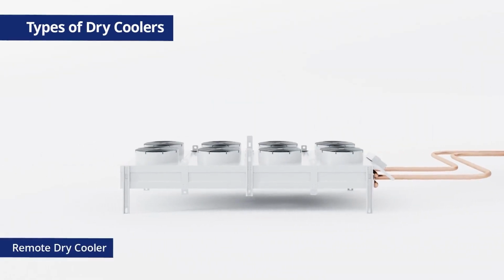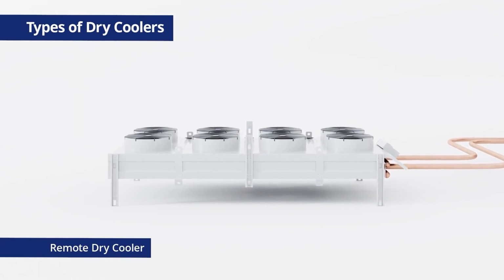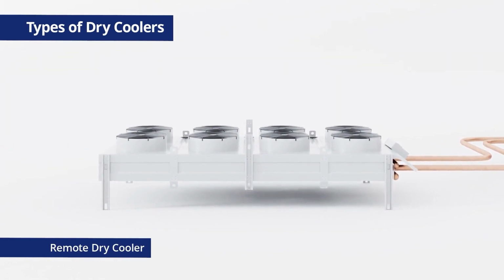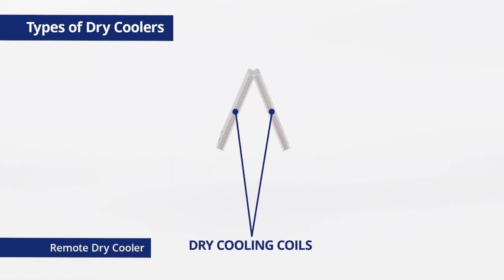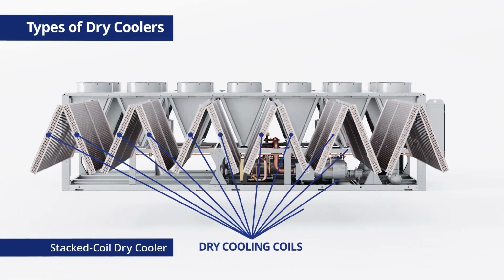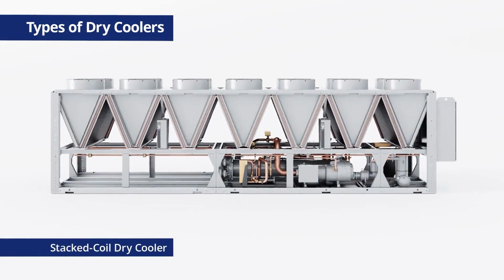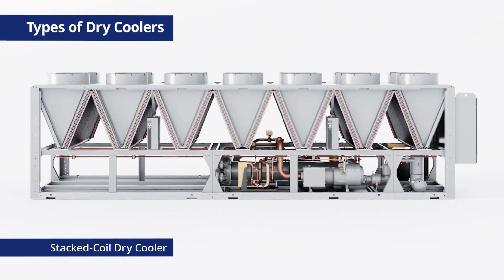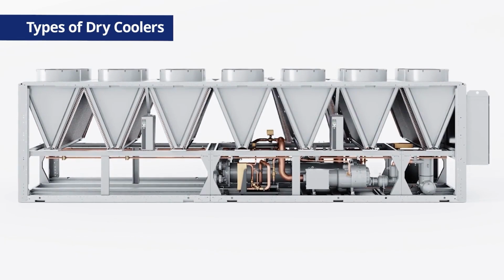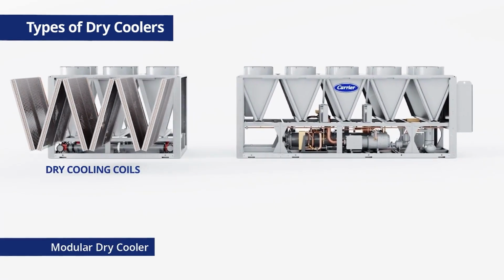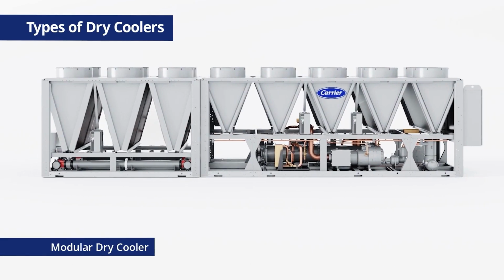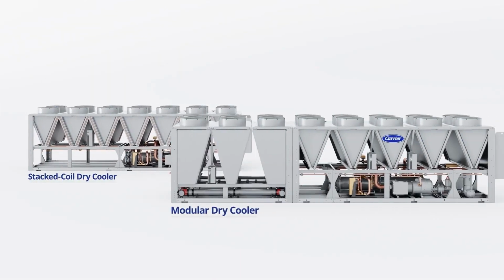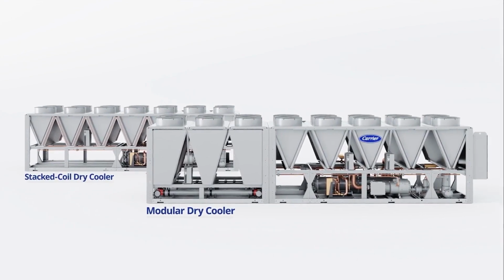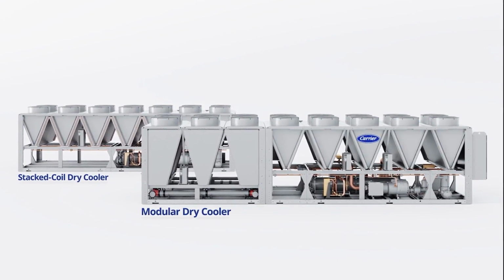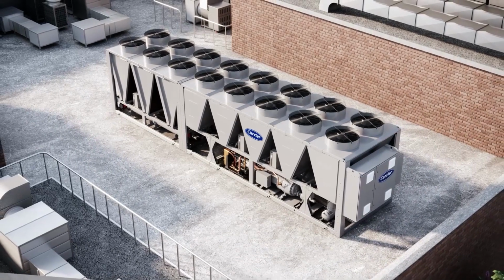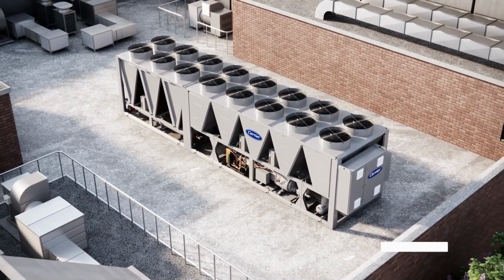The first style is a remote dry cooler. It's typically a general-purpose cooler that sits remote from the air-cooled chiller and is piped together. The second is a stacked coil dry cooler. In this case, the dry cooling coils are mounted or stacked next to the existing refrigerant condenser coils on the chiller. The third is a modular design. It attaches right onto the air-cooled chiller. The last two styles are preferred in many cases because they are designed to integrate directly with specific chillers right from the factory, improving performance. Where there is space available, the modular option can offer superior performance and convenience.